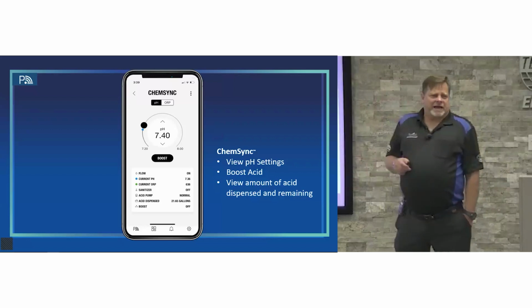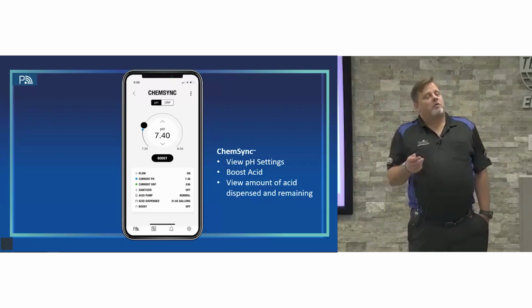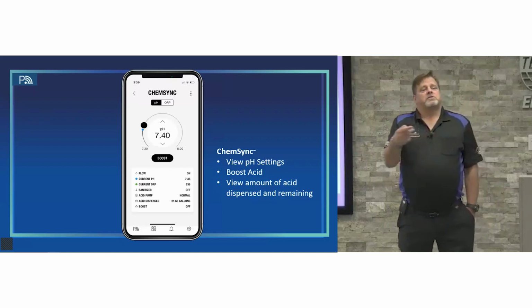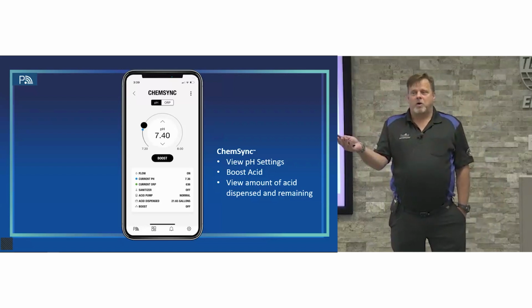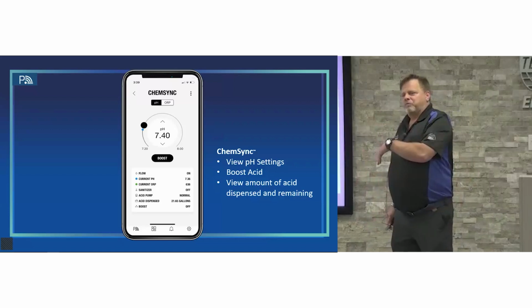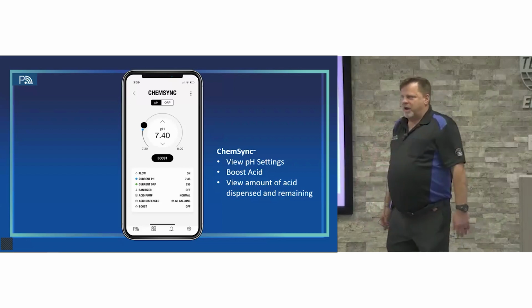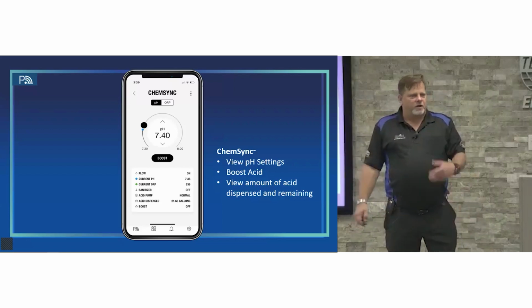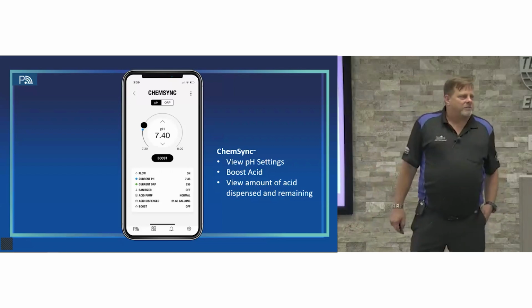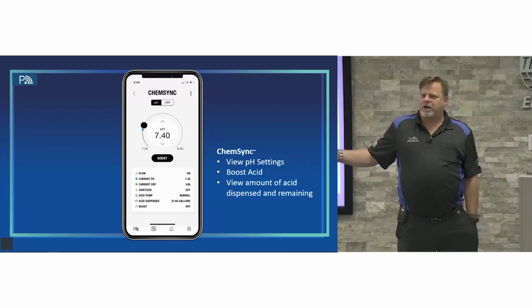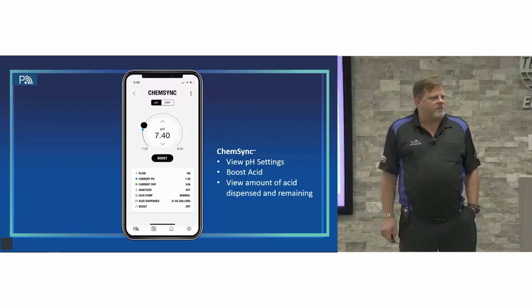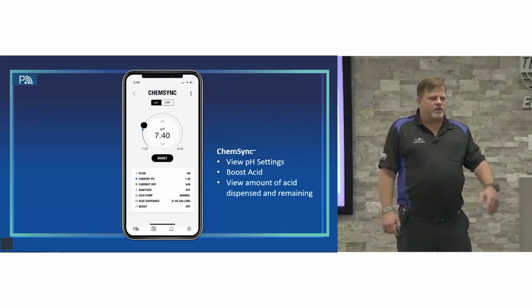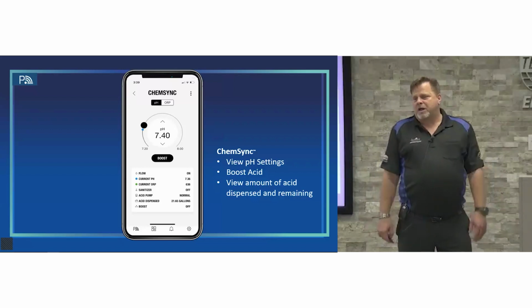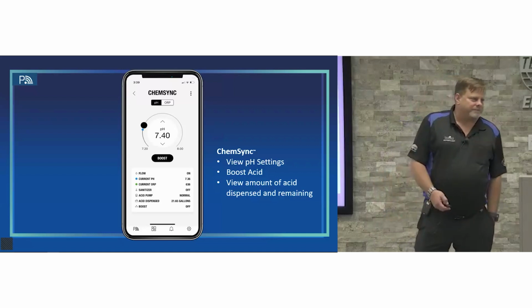Yeah, I'd say somebody's let that go for a while. Now do remember that Stenner does offer 15 and 30 gallon tanks, so you could have a customer who decided a 5-gallon tank isn't big enough for them. They may go to Stenner and purchase a 15 or 30 gallon tank. That's fine, but if you know what tank is there, you know when it needs to be filled. If it's a 15-gallon tank and it's fed 12 and a half, 13 gallons, I'd say it's probably about time to get out there and refill the tank.